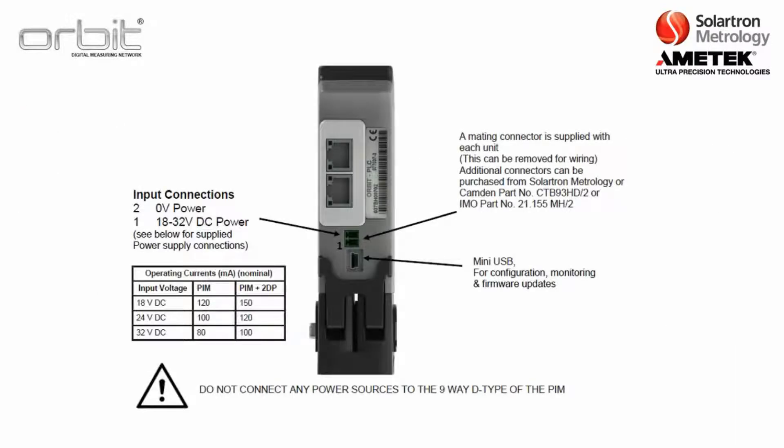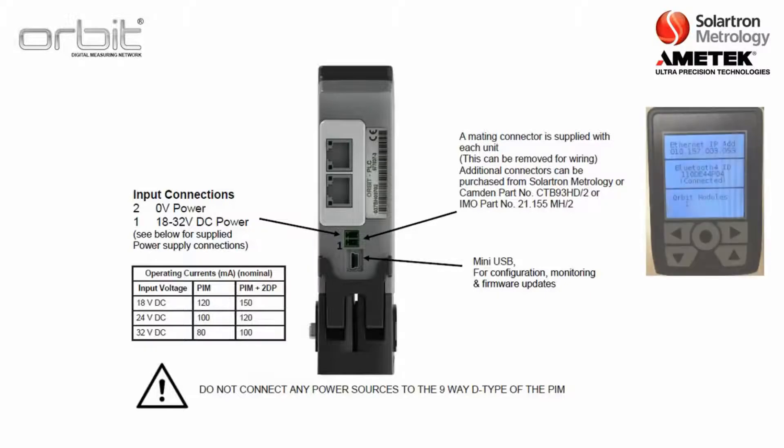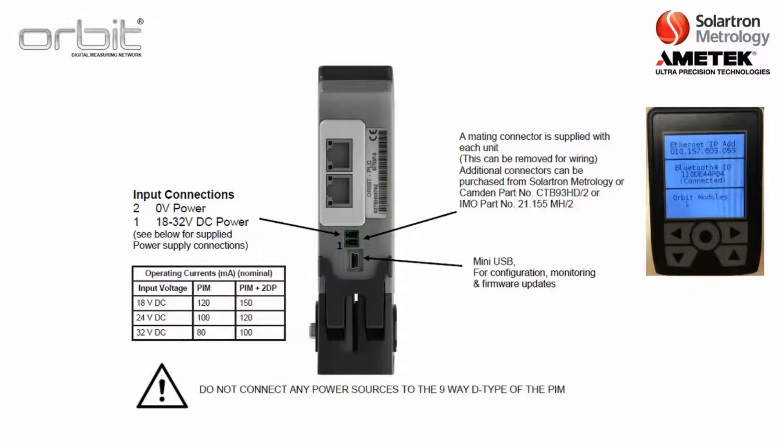Now here's the back of a PIM and there's just a couple of basic components. First of course is the power. Solartron does supply a power pack that you can plug into a wall, but if you want to connect directly to it you just need to have 18 to 32 volts of DC power. There's also a mini-USB port, this is for configuring the PIM. We'll talk about that in a second. Then there is the top screen, which basically just is a monitoring device where you can just see the address, see any Bluetooth IDs, as well as the number of Orbit modules.